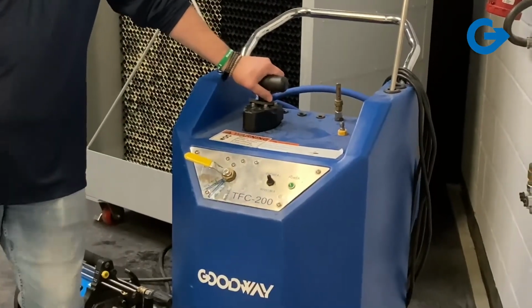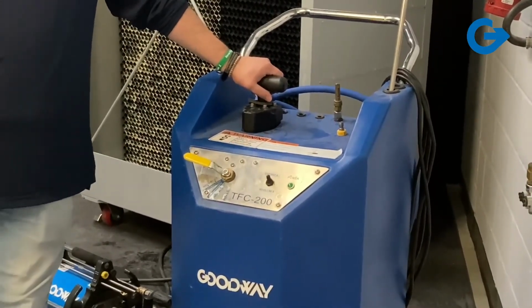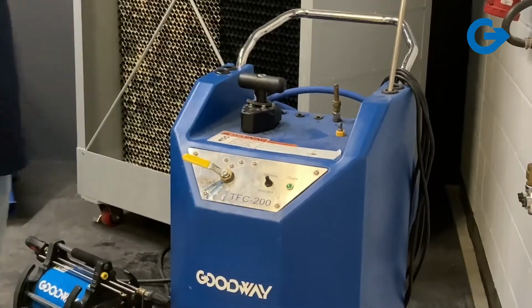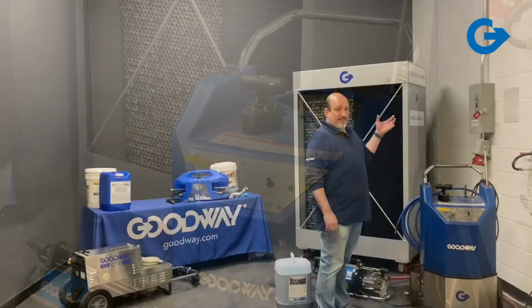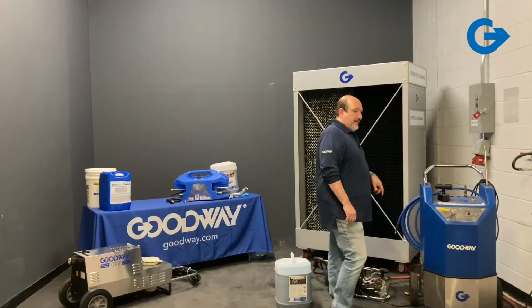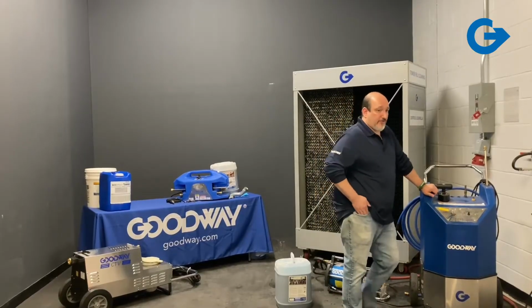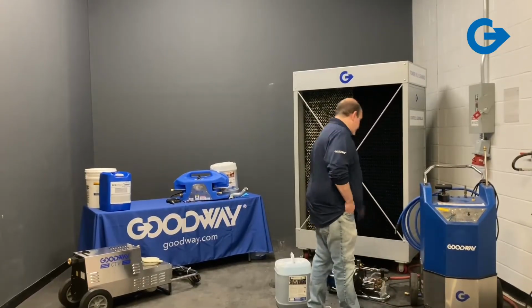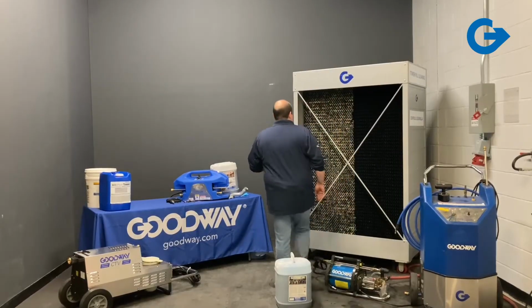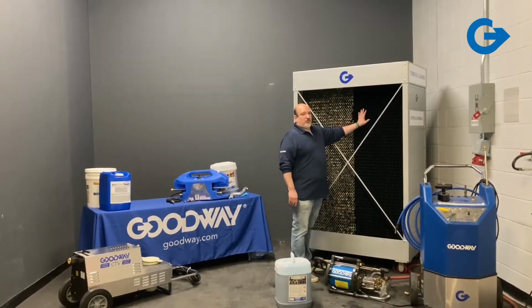Now, we wouldn't recommend a hose for rinsing because sometimes the scale is still clinging to the fill and you need to rinse it aggressively. But we wouldn't recommend a pressure washer either because that can be too aggressive, especially since the fill is made out of plastic and it's often very brittle as well.